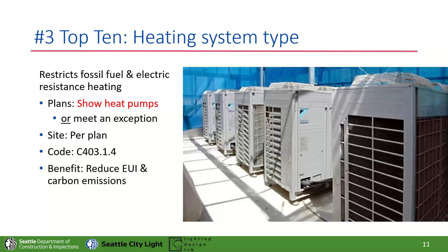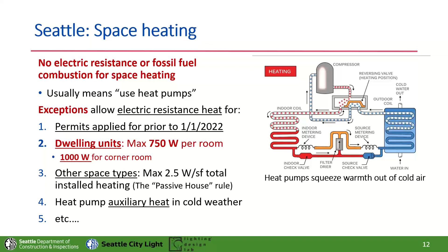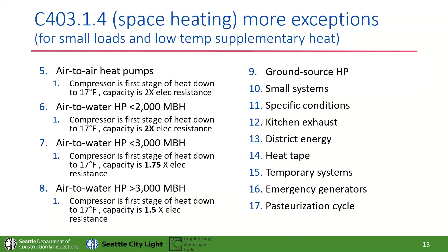So basically you're going to use heat pumps unless you meet one of these many exceptions. The big one shown in red is that in an apartment building, you can have 750 watts per room - we've checked that out and it's generally easily sufficient to run your building. Then there's lots of other exceptions: the ones on the left are mostly about where you can have supplementary electric resistance heat kick in and how much there can be, plus other specific exceptions for small or temporary loads.